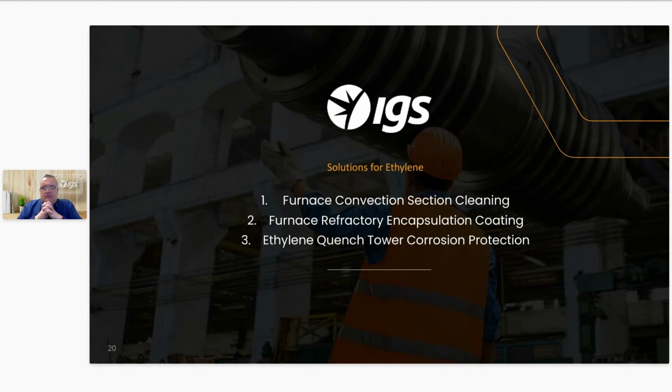We also have some other products and product lines we do for online services for all furnaces, including ethylene. We have a hot refractory repair service. So if you're suffering any hot spots on your unit, we can repair those hot spots without actually shutting the unit down. And I'm sure maybe we can set up another webinar which goes through some of those services in more detail. We have hot access creation, as I touched on earlier, which we can use to create openings for the cleaning without having to actually shut the furnace down.